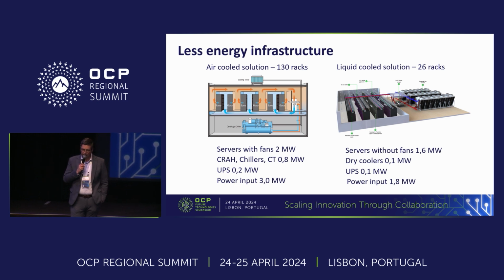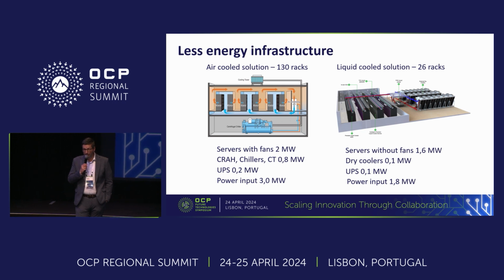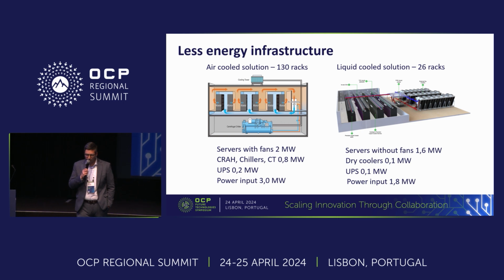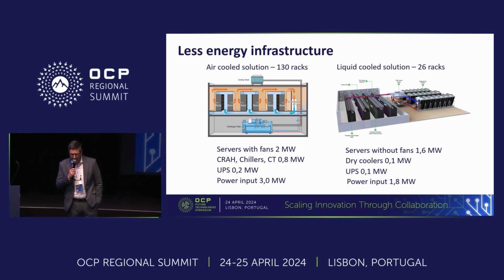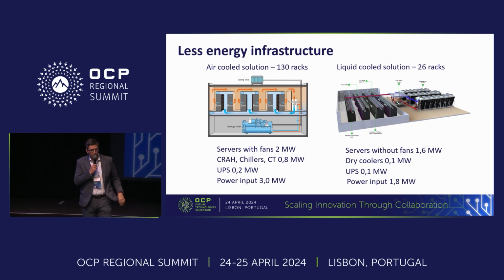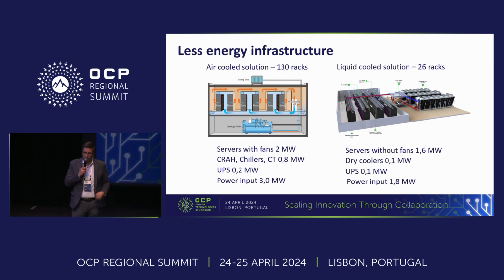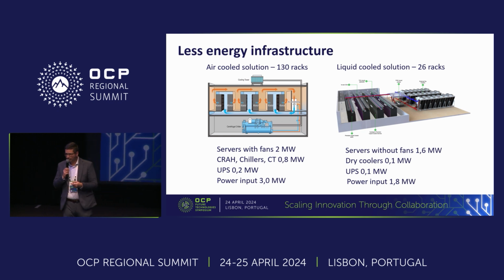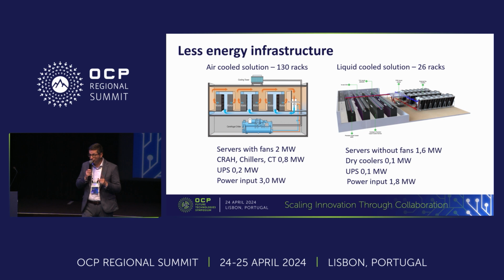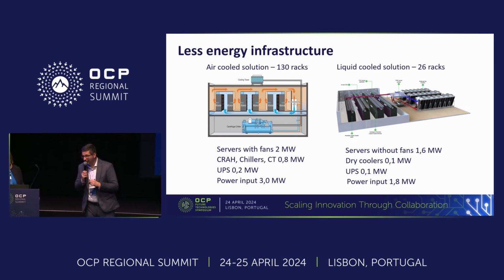Both systems also need a backup system, with UPS provided for each. The traditional air-cooled system needs 200 kilowatts, and the liquid-cooled system needs 100 kilowatts. All in all, as a consequence, the energy provided for the liquid-cooled system is 1.8 megawatts, which is 40% less.